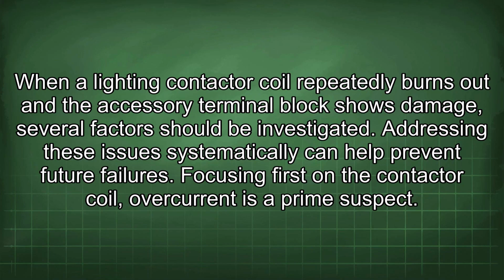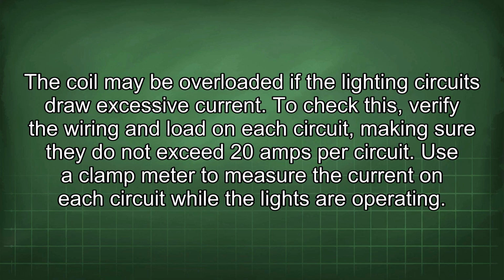When a lighting contactor coil repeatedly burns out and the accessory terminal block shows damage, several factors should be investigated. Addressing these issues systematically can help prevent future failures. Focusing first on the contactor coil, overcurrent is a prime suspect. The coil may be overloaded if the lighting circuits draw excessive current.